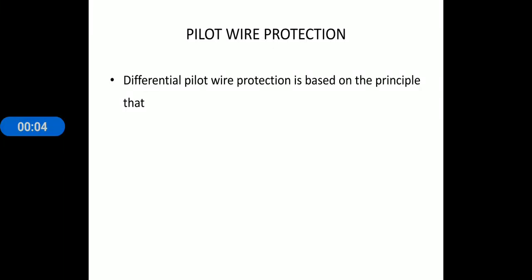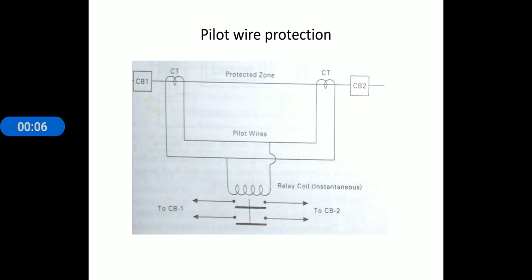Next one, pilot wire protection, or differential pilot wire protection. It is also based on the same principle used for differential protection of alternators, transformers and bus bars. Here also the same principle is applied, and that principle is the circulating current principle.